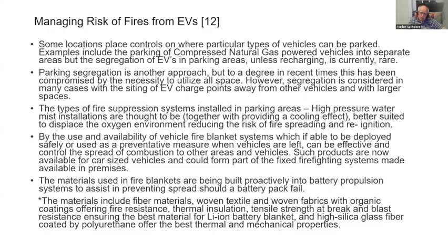Parking segregation is another approach, though this has at times been compromised by the need to utilize available space. Still, segregation is considered in many cases, siting EV charge points away from other vehicles and with larger spaces. Fire suppression systems installed in parking areas include high-pressure water mist installations, which provide a cooling effect and are better suited to displace the oxygen environment, reducing the risk of fire spreading and reignition.